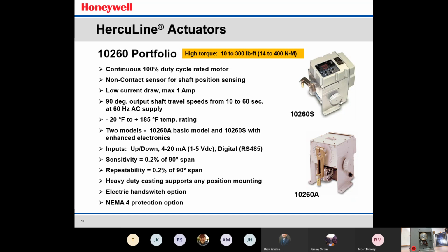Sensitivity adjustment is 0.2% of 90-degree span, which is a very tight tolerance, and the repeatability is 0.2% as well. It comes in NEMA 4, which is an option on the actuator, and as we were talking about earlier, you can also have the electronic hand switch, which is the auto manual switch option as well.